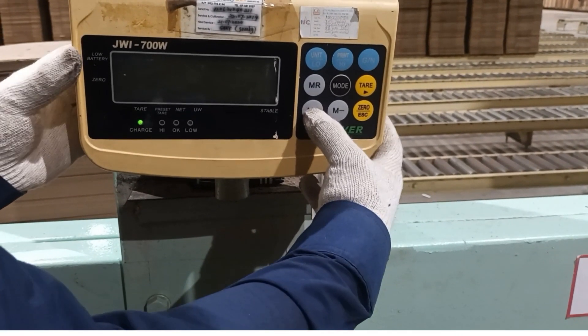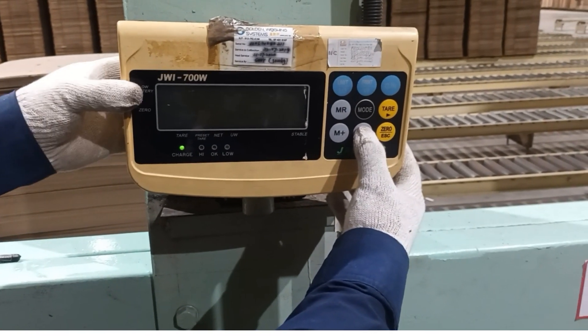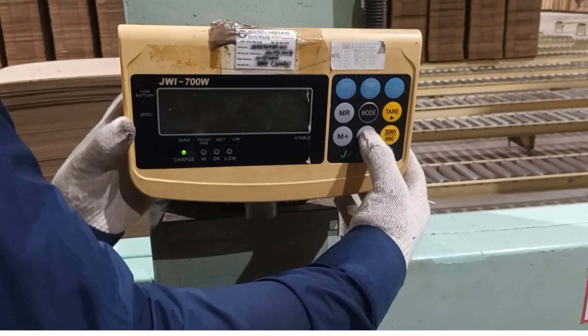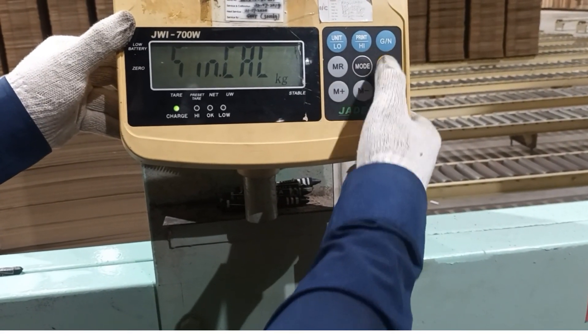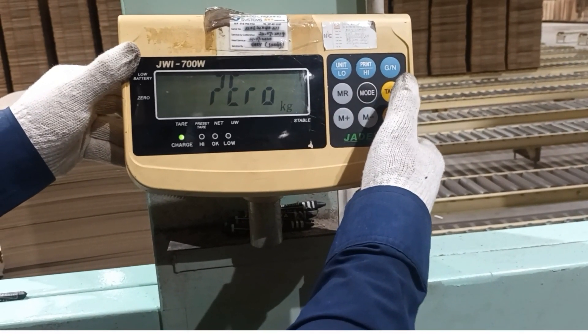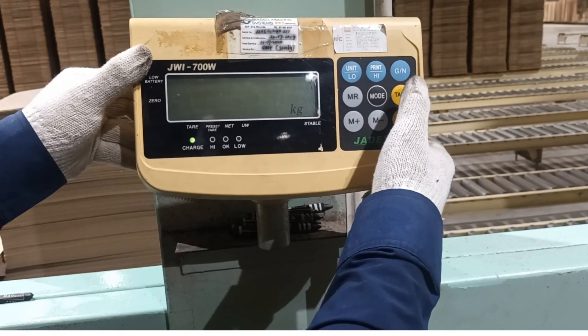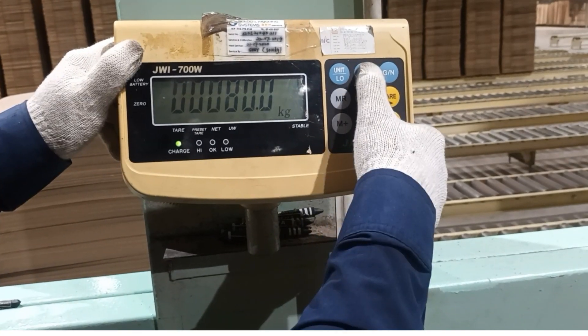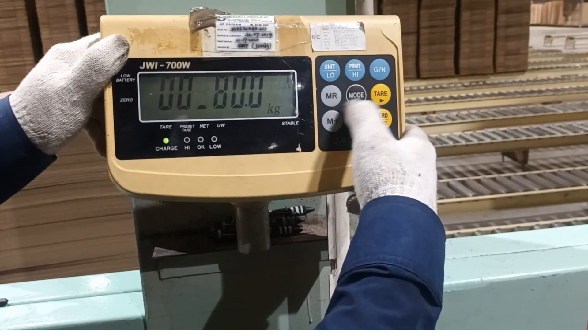Hello everybody. I will do an adjustment for a platform scale, model JWI-700W. First, I will turn on the scale and press the M+ key. Then I will insert the key to adjust the capacity — I want to calibrate the capacity.